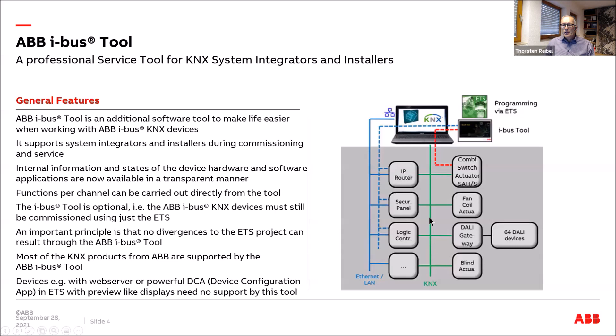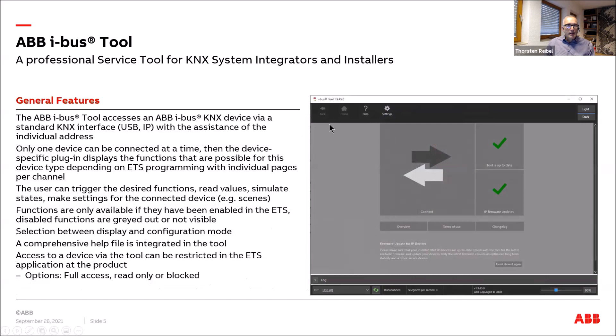On the right you see the typical constellation: you have your KNX system, a PC with ETS to program everything, and additionally the ABB i-bus Tool installed. The prerequisite is a Windows PC. You connect via USB or IP interface — just like with ETS — and you need at minimum the individual address of the device downloaded. Then a device-specific plug-in is shown with all functions and individual pages per channel for multi-channel devices.